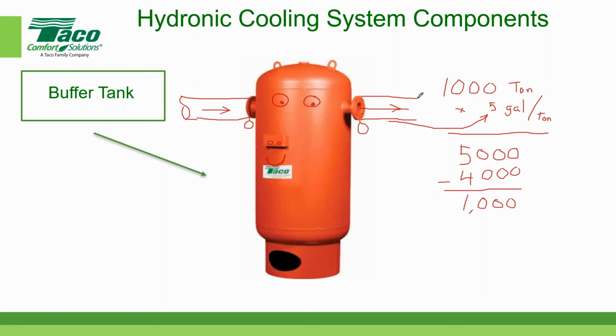And so the buffer tank is always 100% full of water, as opposed to an expansion tank. Typically, an expansion tank is filled somewhere between 30 to 50% with water. So buffer tanks are 100% full, and they act like a battery or storage. An expansion tank does not store water. It allows it to expand into the bladder. And usually it's a fraction of the total volume of the tank itself. Did I make that as clear as mud, Brett?